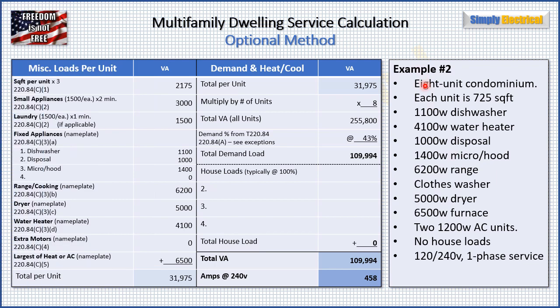Starting with square footage: 725 square feet per unit multiplied by three gives us 2,175 VA. We add two small appliance circuits for 3,000 VA, and a laundry circuit for 1,500 VA. Fixed appliances include a dishwasher, disposal, and micro hood at their listed values. Range at 6,200 watts. Dryer at 5,000 watts. Water heater at 4,100 watts. The largest of heating and cooling is the furnace at 6,500 watts.